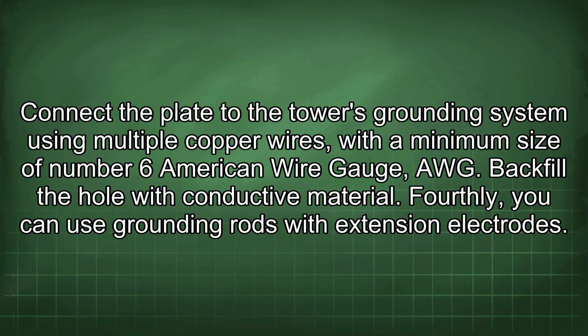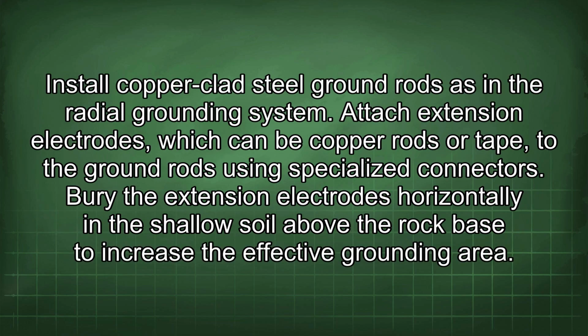Fourthly, you can use grounding rods with extension electrodes. Install copper-clad steel ground rods, as in the radial grounding system. Attach extension electrodes, which can be copper rods or tape, to the ground rods using specialized connectors. Bury the extension electrodes horizontally in the shallow soil above the rock base to increase the effective grounding area.